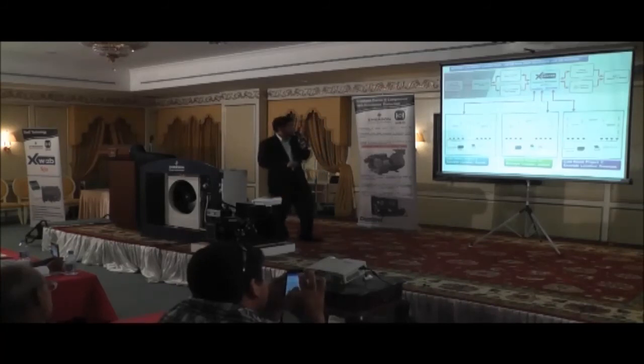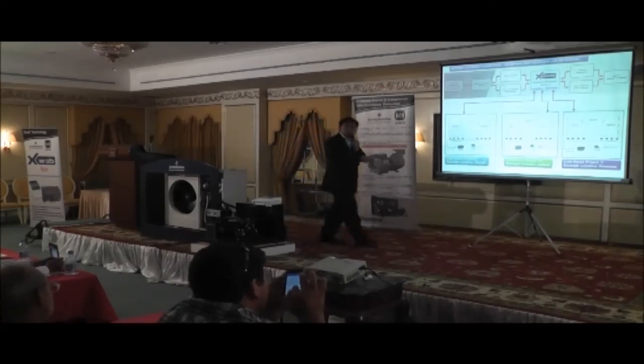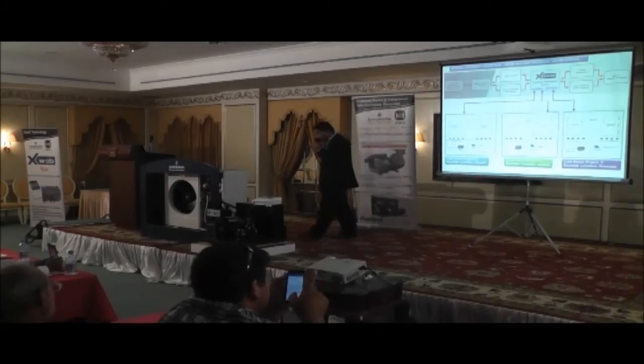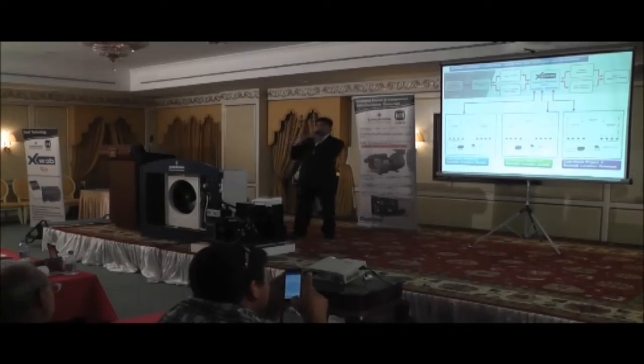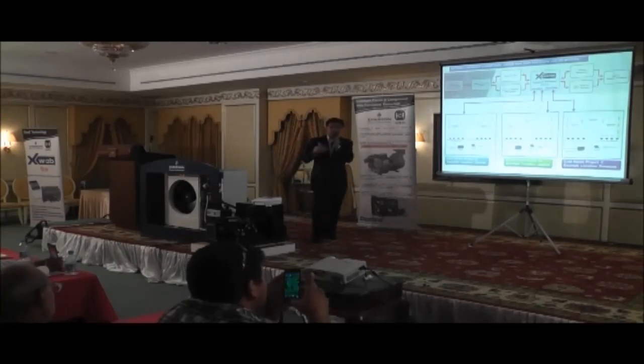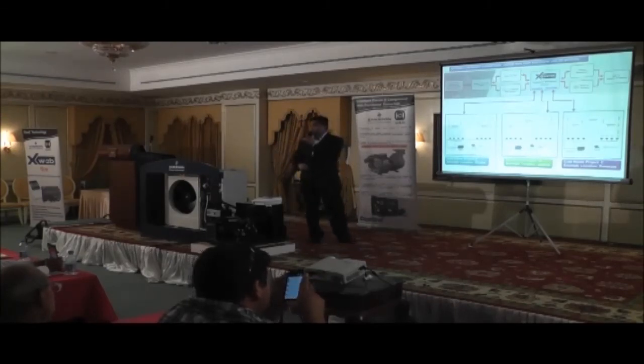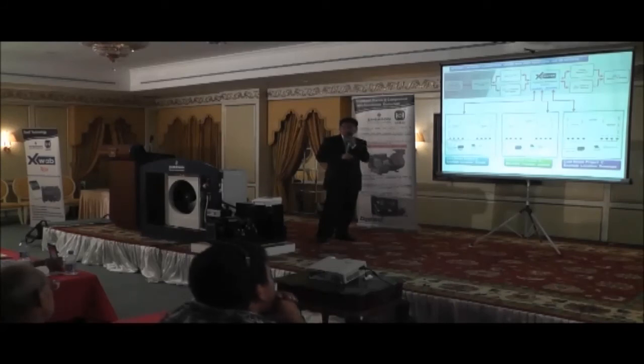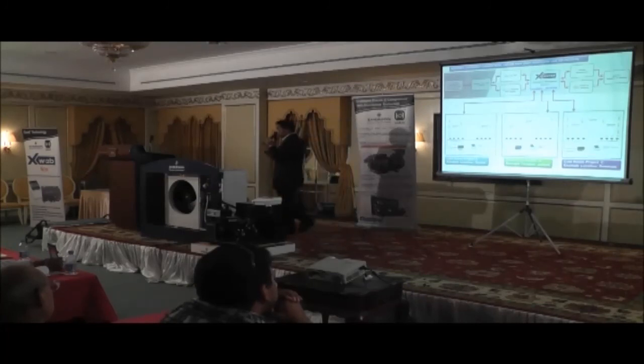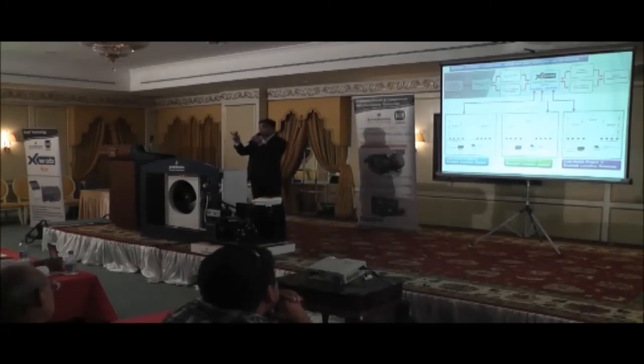For example, this one is a freezer room. After you remove all the products, the store owner asks, can I use this room as a chiller? It is a freezer room, and I have some products, but I urgently need a chiller temperature, not freezer. So from the X Center, you can change the temperature of this room to a chiller temperature. For example, if your controller is capable of both medium and low temperature, you can do that without flying from Jeddah to Riyadh, just sitting in front of your computer.